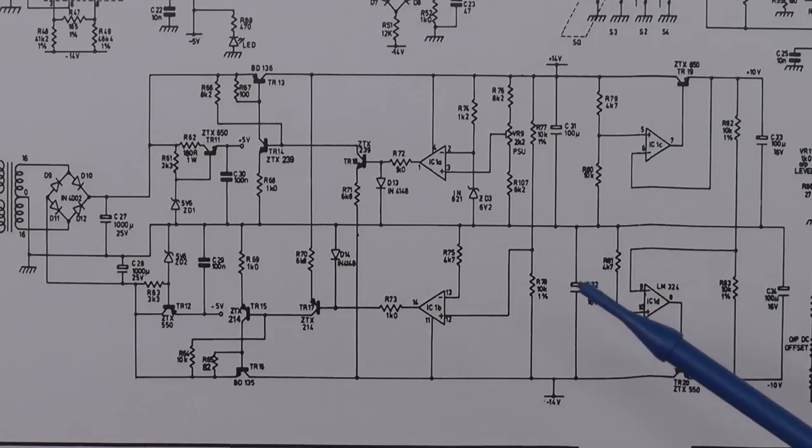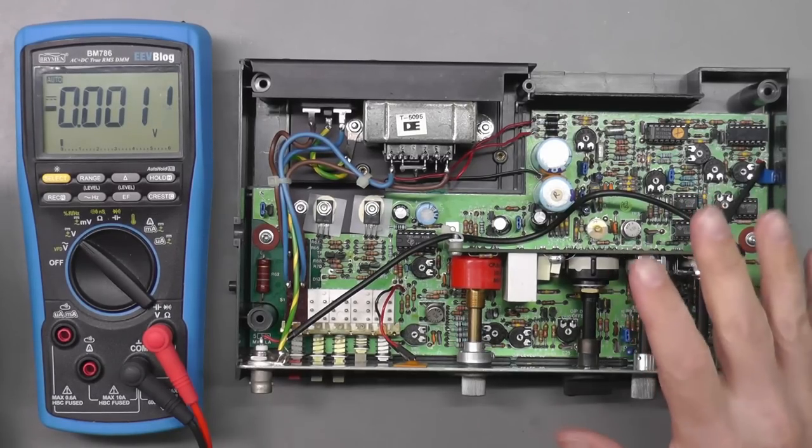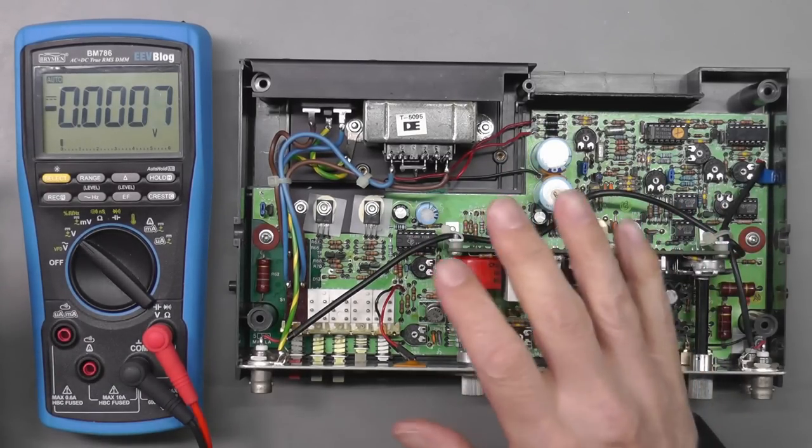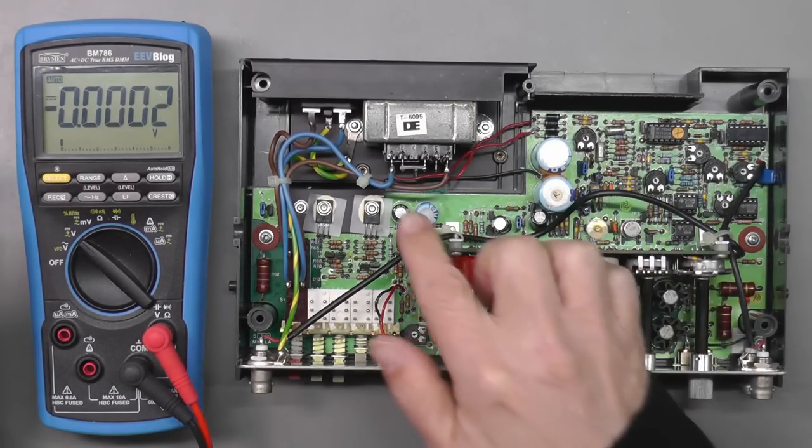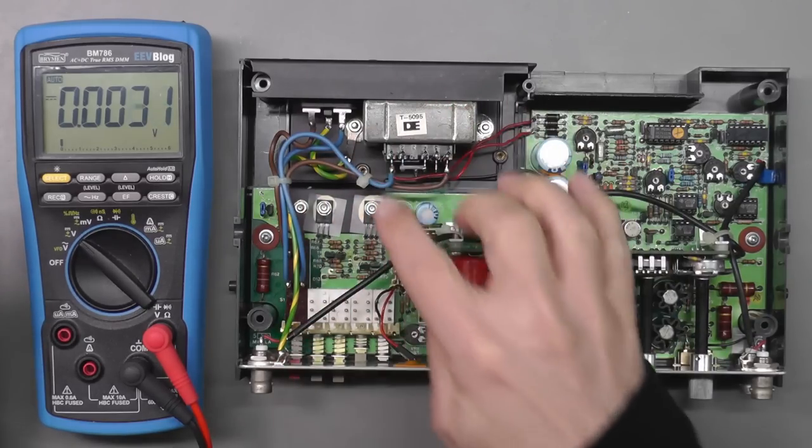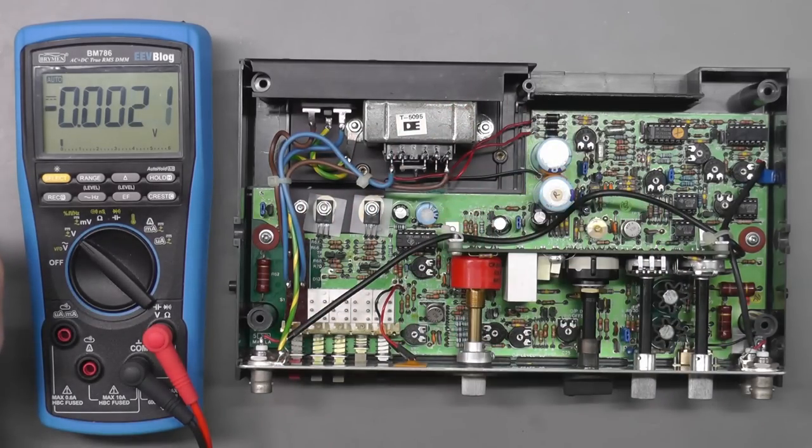Let's get back to the unit, power up, and see if those power supplies are intact. Safety first though—there's no fuse in this unit, and we've got some live terminals, so I'm going to mask and tape them off to keep myself safe.